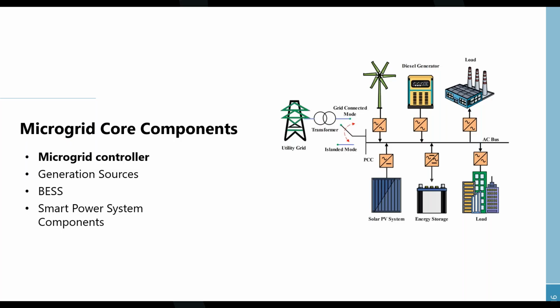One of the key features there is the generators. You want your generators to provide redundancy and efficiency, so at least two generators are recommended, especially in combination with a large PV system or wind power generation system. The other feature is the battery energy storage system, which exists to reduce wear and tear on your generator, improve power quality, and increase reliability for the microgrid.